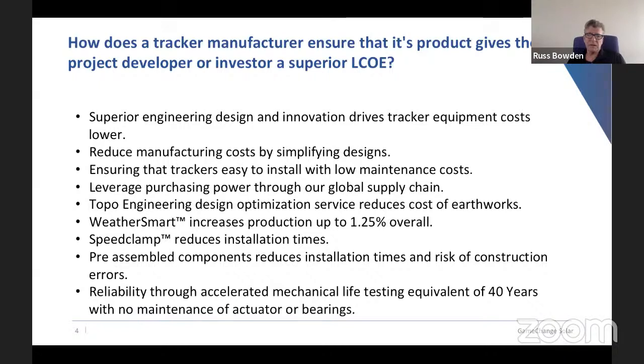Another innovation we have is supplying pre-assembled components. Some components that require precision assembly and torquing, we do those in the factory and deliver them pre-assembled onto the site, which reduces installation times and risk of construction errors. If there are construction errors, and let's say you're building a 100 megawatt plant and the guys on site make an error putting modules on, it's quite a costly exercise to take those modules off and make a correction. So by doing the pre-assembly, we reduce that risk of construction errors.